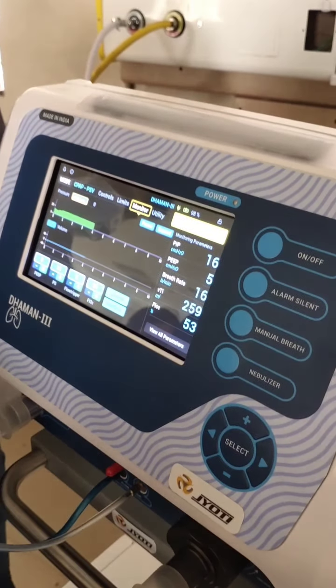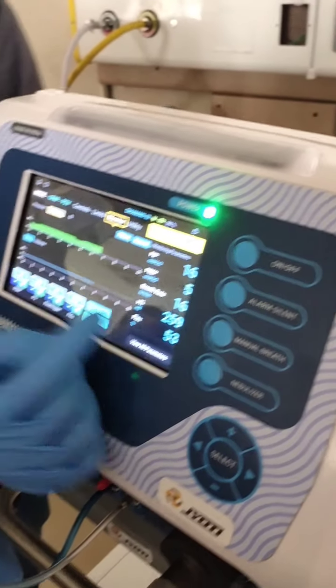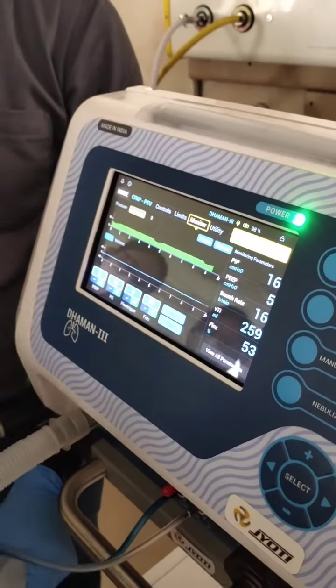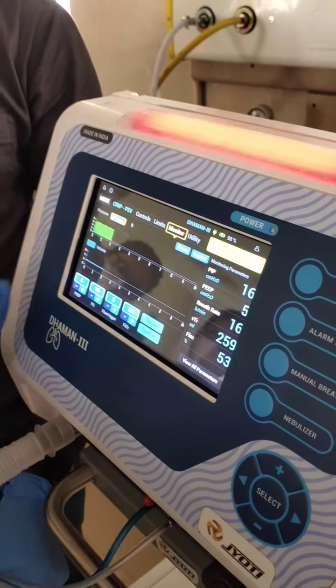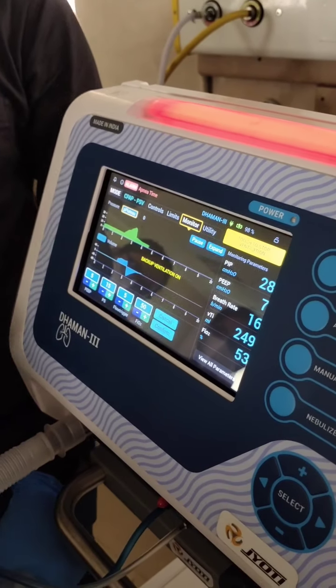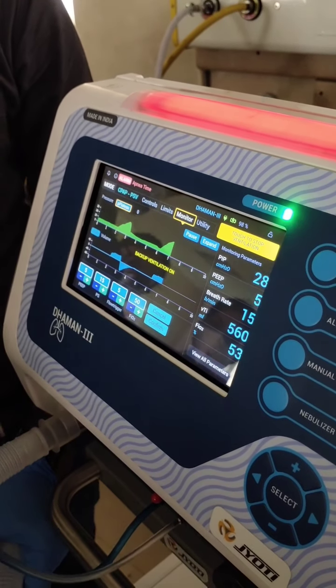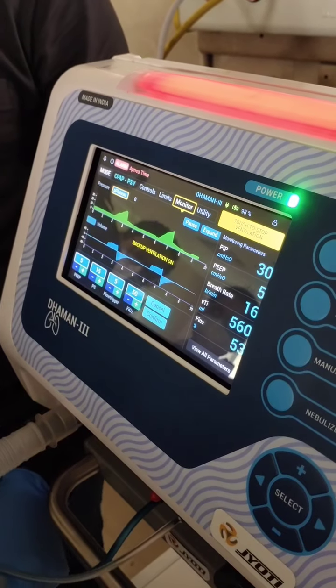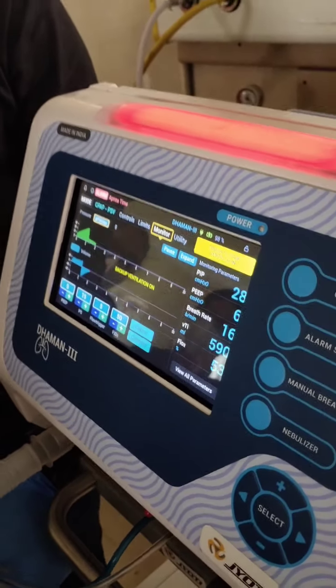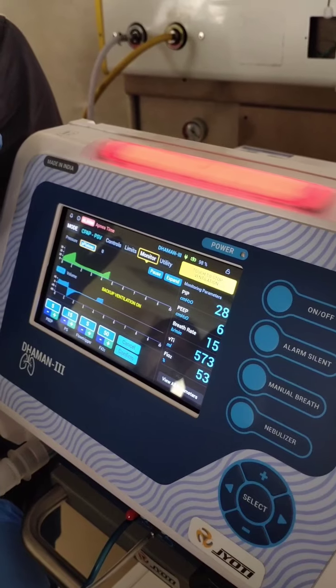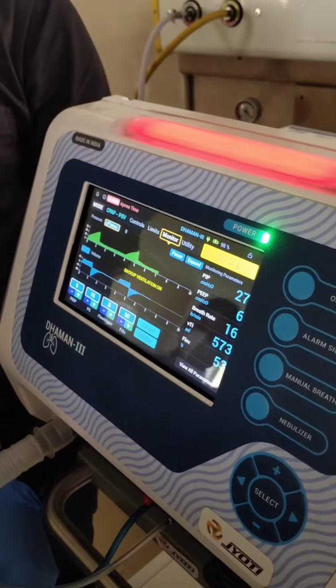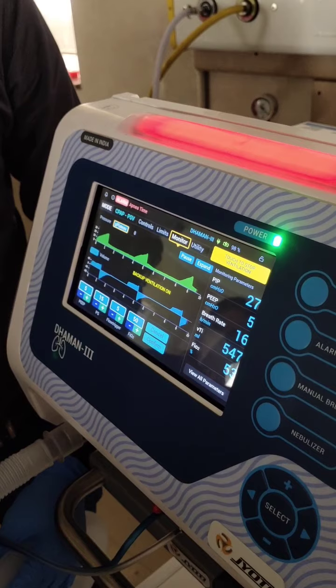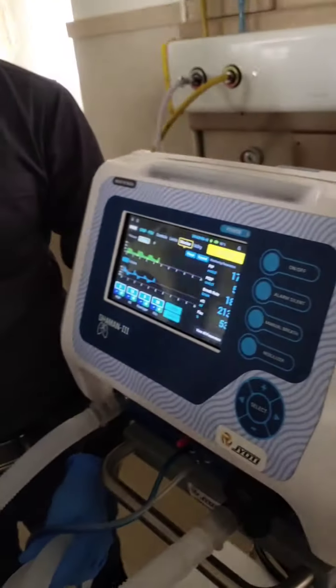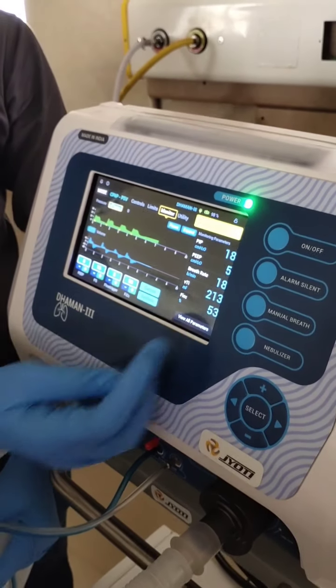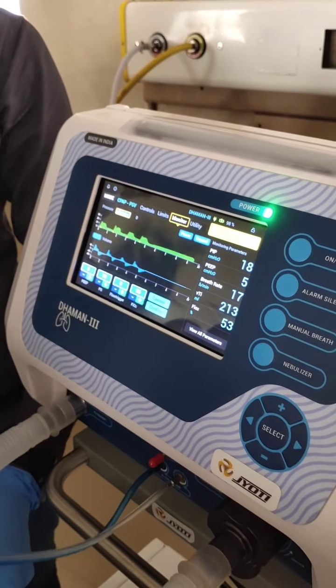Yeah. So at that time you notice that the tidal volume will vary. You are setting 500, but the value will become 200 or 600. It will vary because it is either volume control or pressure control. In pressure control, the tidal volume will vary, because volume control means the volume will be continuously supported at the set value. But we are doing pressure control. The pressure is going to that test lung. If I am using the test lung, the patient lung will be there, so they have a separate lung volume. So at that time, the tidal volume will vary. So that's why the ma'am asked about it last night.